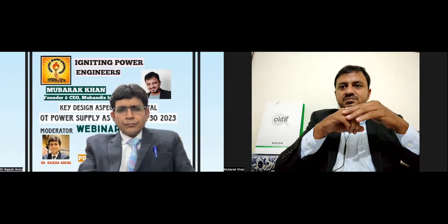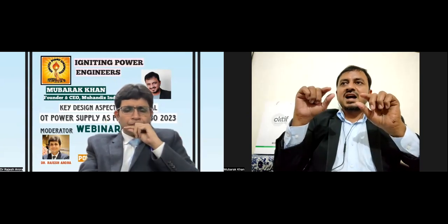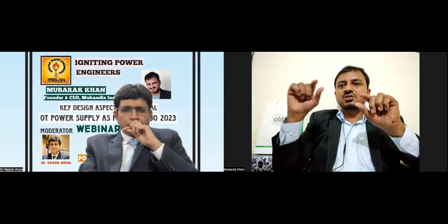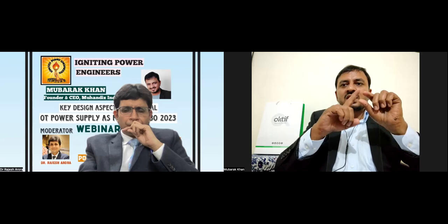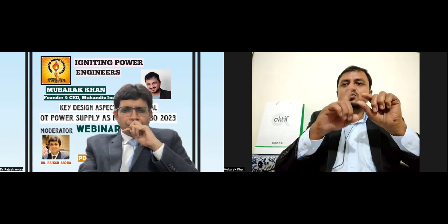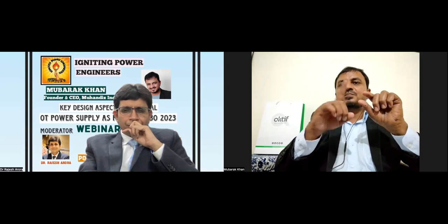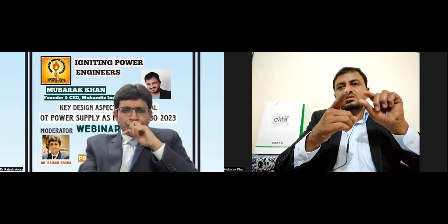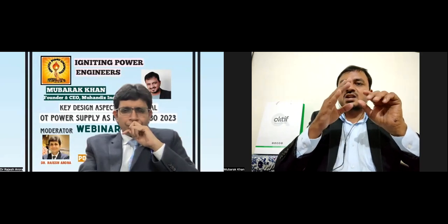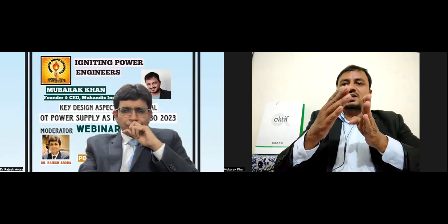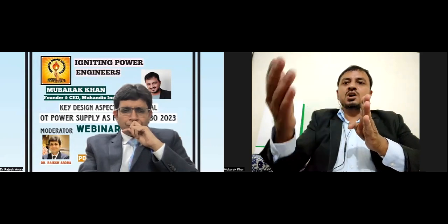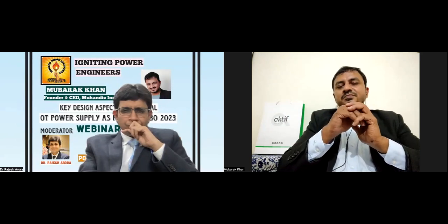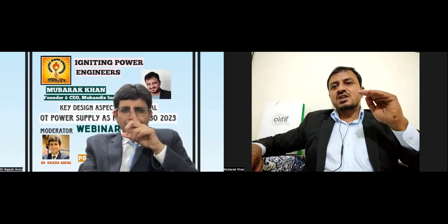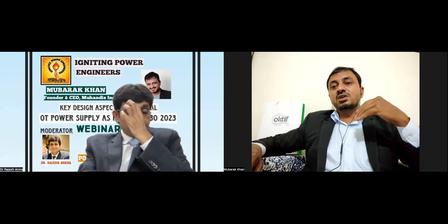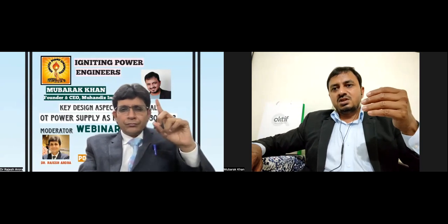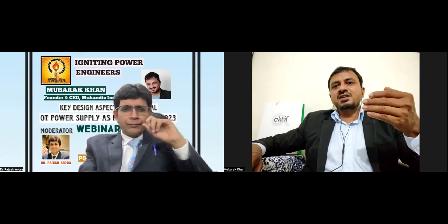Now, if this power is coming to the operation theater through an IT system, I am going to connect a single phase transformer whose primary and secondary are both single phase, both 230 volts. The purpose of the transformer is only to isolate the power supply from the input to the operation system. That is the only purpose. Okay, thank you very much. The size of the transformer can be 3, 6, 10, whatever, depending on the requirement of the operation theater load. If the operation theater is consuming only 8 kVA, we can have 8 kVA.